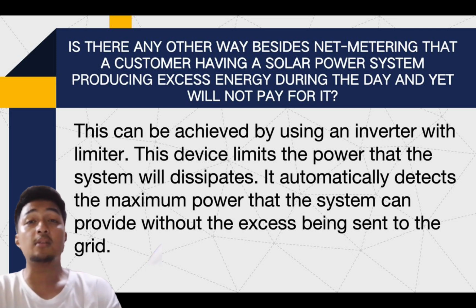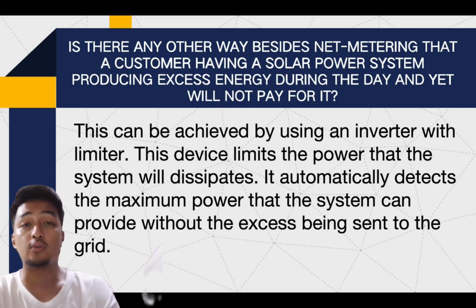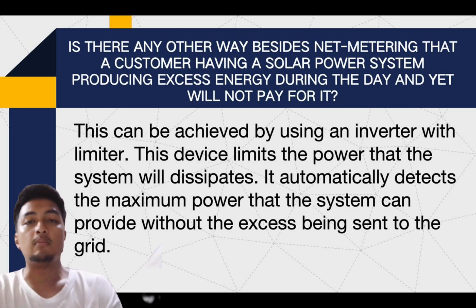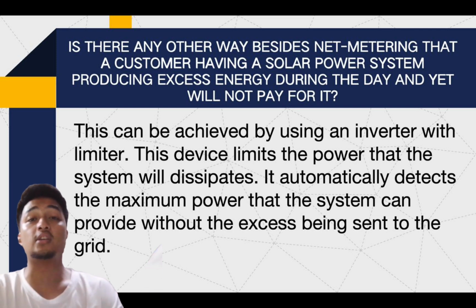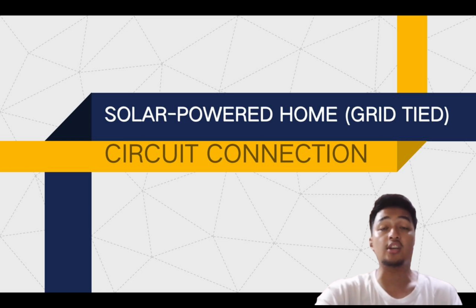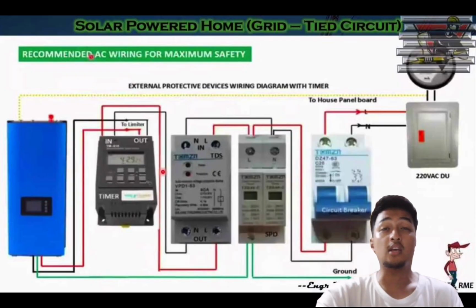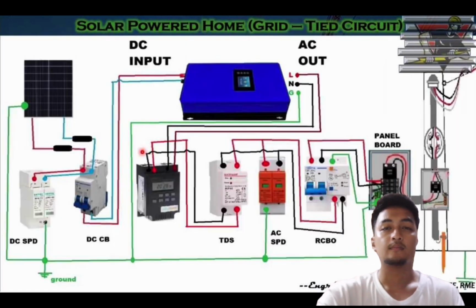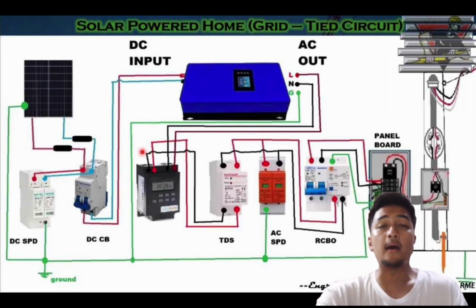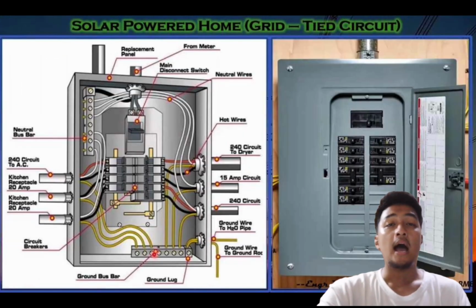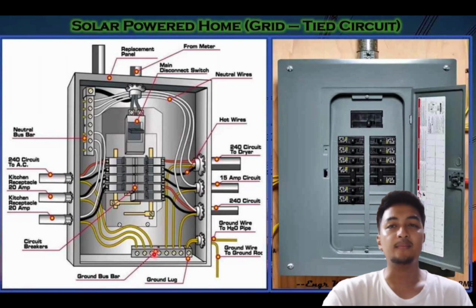Is there any way besides net metering for a customer having a solar power system that produces excess energy during the day to avoid paying for it? This can be achieved by using an inverter with a limiter. This device limits the power that the system will dissipate. It automatically detects the maximum power that the system can provide without the excess being sent to the grid. So let me show you how the circuit connection looks. And this one is the recommended AC for maximum safety. And this one is how the solar energy works from solar panel to panel board. And the last one is how the circuit breaker looks from outside to inside.